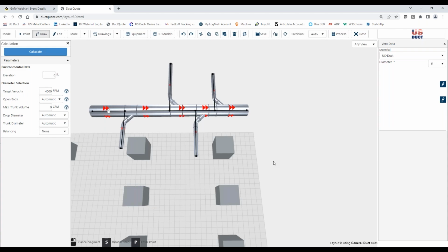Okay. Now, we've got an 18-inch duct maintained the entire length. And I see this fairly often with folks who think that it will be a great way to save money because they've already got, let's say in this case, 18-inch duct, and they're going to reuse it for the entire trunk.